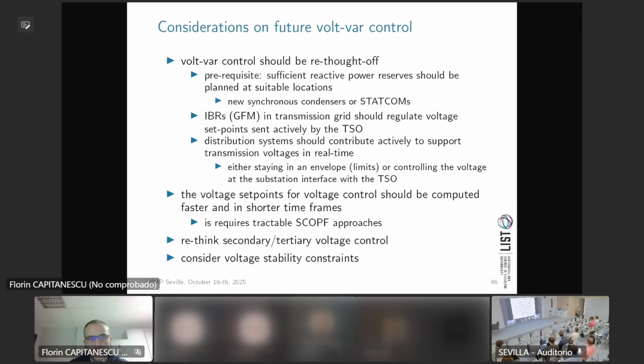But classical volt-var problems and classical reactive power problems are still there, and we need to solve them. So at the very beginning of your presentation, you said that the quality of the reactive power provided by renewable energy sources is not as good as, let's say, synchronous generators. I do not fully agree with this, because at the end of the day, a voltage converter as an interface of a PV power plant has almost the exact model as a synchronous generator.